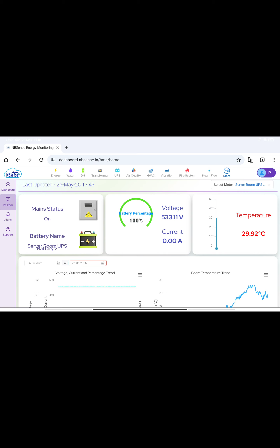Next we have UPS monitoring, where we have the whole UPS bank solution, and also individual battery cell-level health monitoring. At the whole battery bank level, we can see total string voltage, current, temperature, main status on/off, and battery room temperature. At the individual cell level, we are able to see individual cell health monitoring.